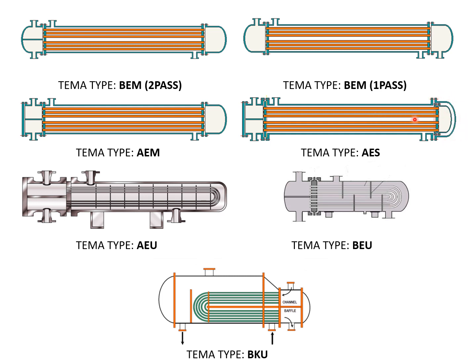Your tube will be moving inside, so that the expansion does not disturb the mechanical design of the exchanger. All this comes into mechanical design. When you design the exchanger and you see too much thermal fluctuation, in that case you will go with the AES type of heat exchanger.